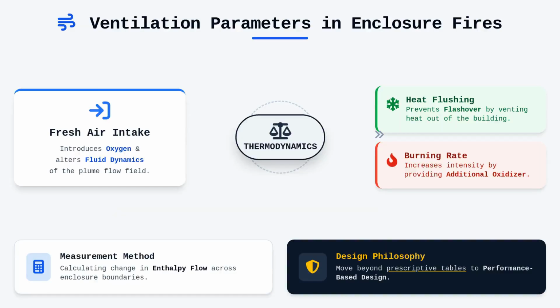Ventilation parameters add a layer of complexity that often dictates the outcome of an enclosure fire. Fresh air intake provides oxygen, but it also alters the thermodynamics of the plume by changing the fluid dynamics of the flow field. Excessive ventilation can flush the heat out of the building, potentially preventing a flashover, but it can also increase the burning rate by providing additional oxidizer.